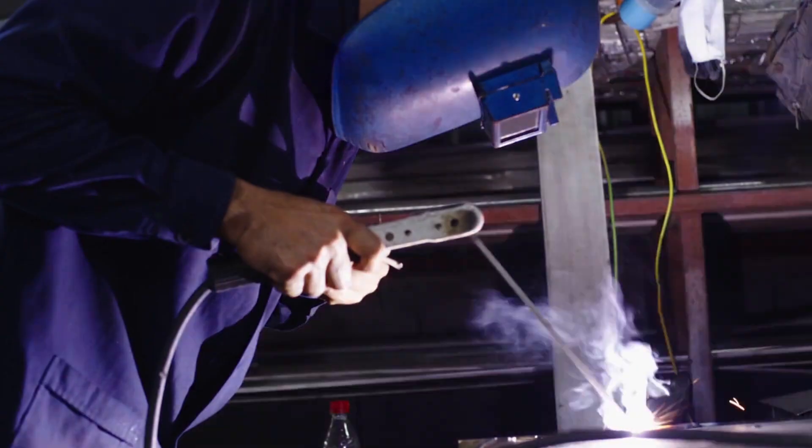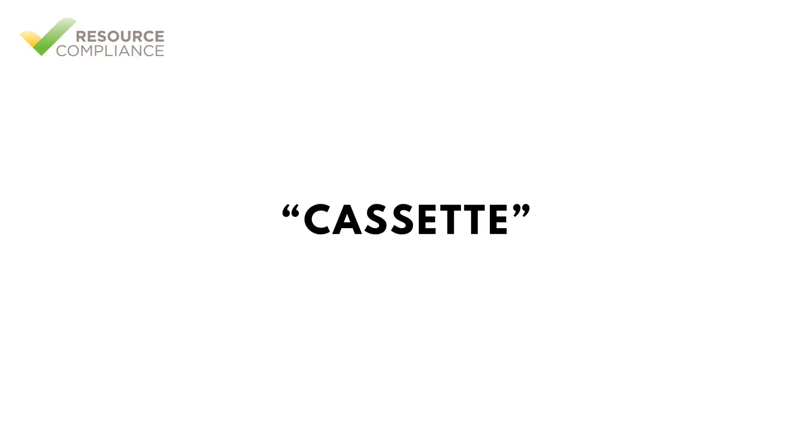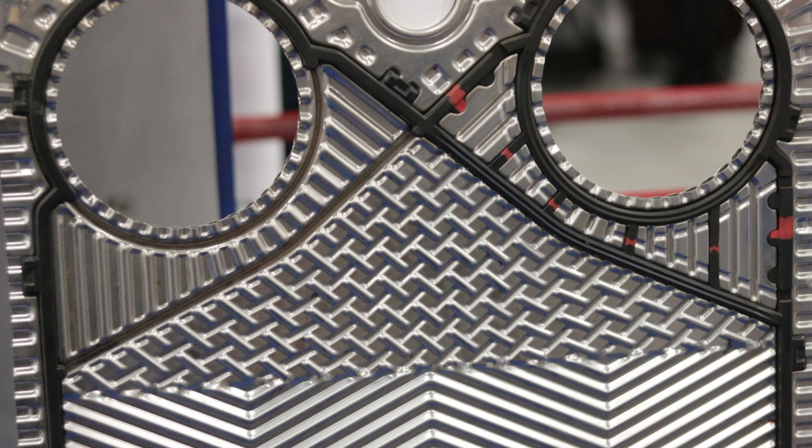Plate and frame heat exchangers are attractive because of their compact size, high efficiency and ease of maintenance. A pair of plates is often called a cassette. The number of cassettes required will depend on the evaporator load. The cassettes are held together in a frame. The frame can be adjusted to add or remove plates if the refrigeration needs change.